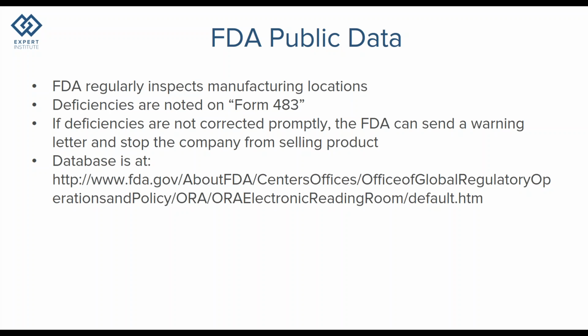So these people typically are trained in auditing techniques. They may be subject matter experts for orthopedics or cardiovascular. They might have an engineering background. They could be almost anything. But most of the people that go out and do inspections for FDA are really well trained, and they know what they're looking for. So the Form 483 is what you would consider an expert's opinion of what the manufacturer has either complied with or if there are deficiencies.